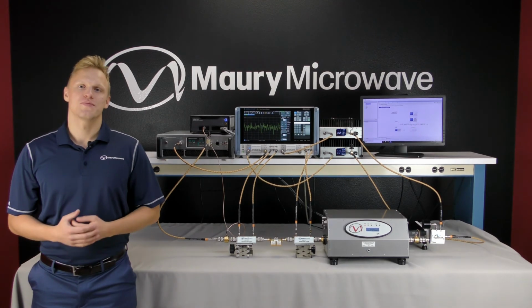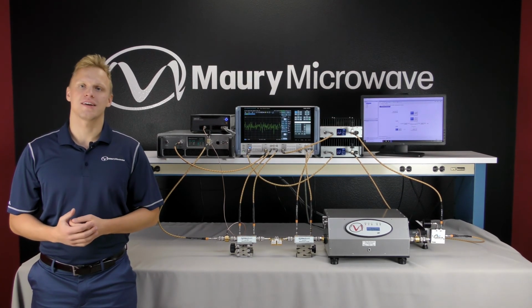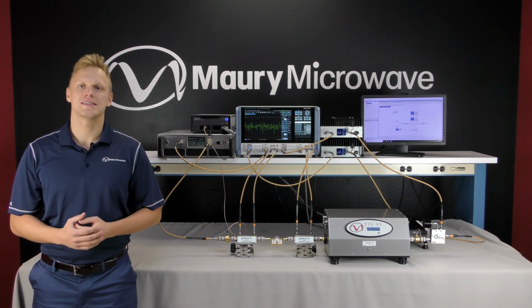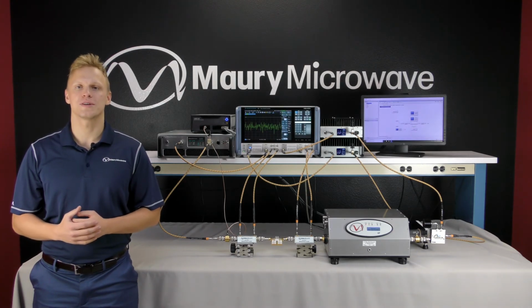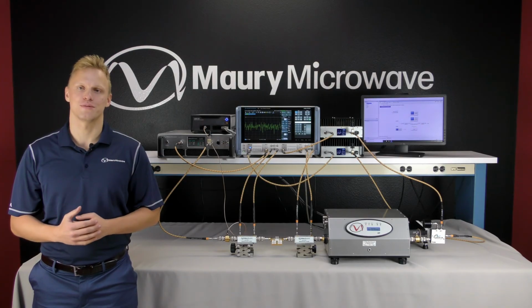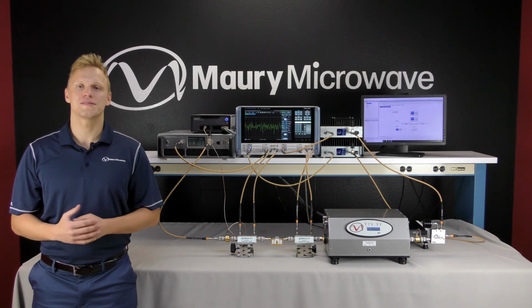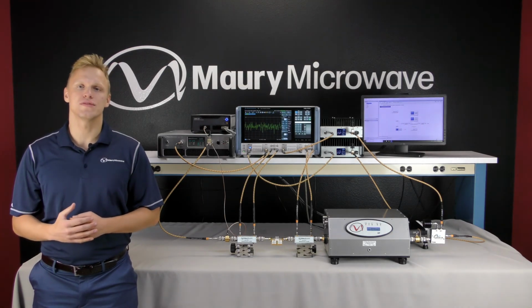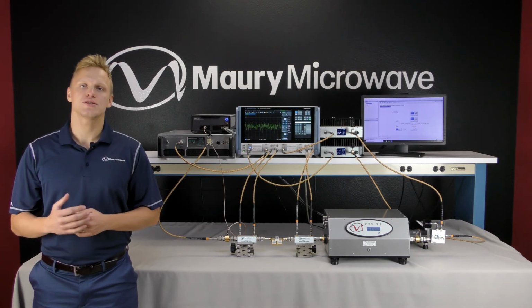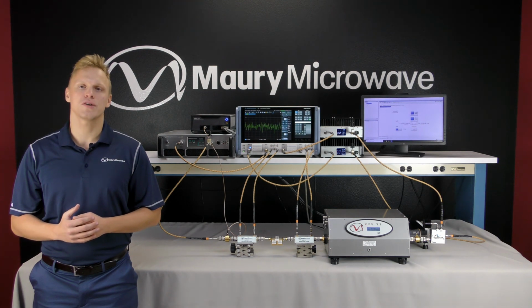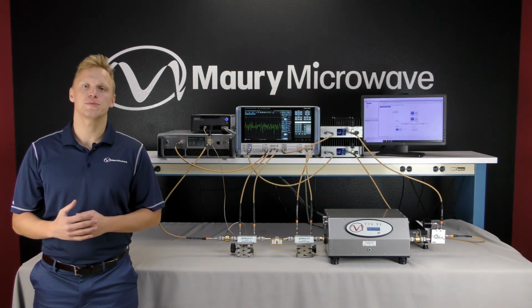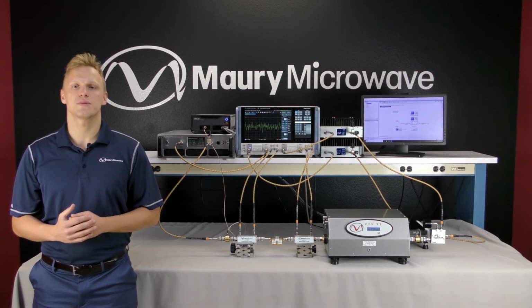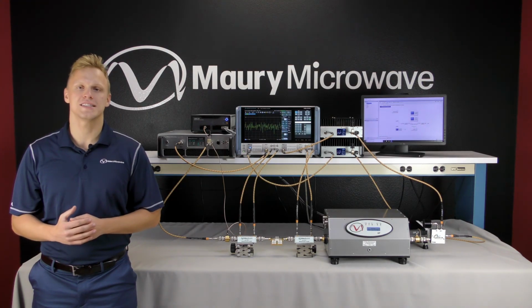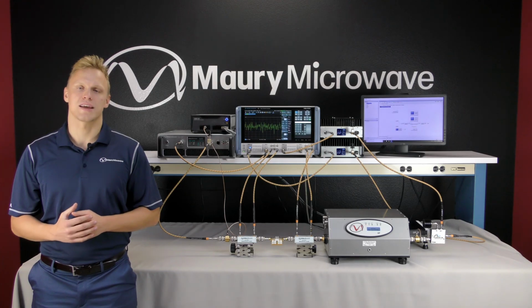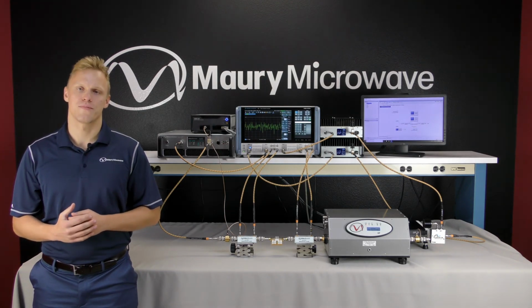So to summarize, load pull is a powerful tool to characterize the behavior of a device under test under linear and non-linear operating conditions as a function of load impedance. Maury Microwave's hybrid active harmonic vector receiver load pull methodology allows to quantify the effects of harmonic termination impedances on the device performance at fundamental frequency and enables computation of various device parameters from vector measurements of incident and reflected waves at the calibrated DUT reference plane.